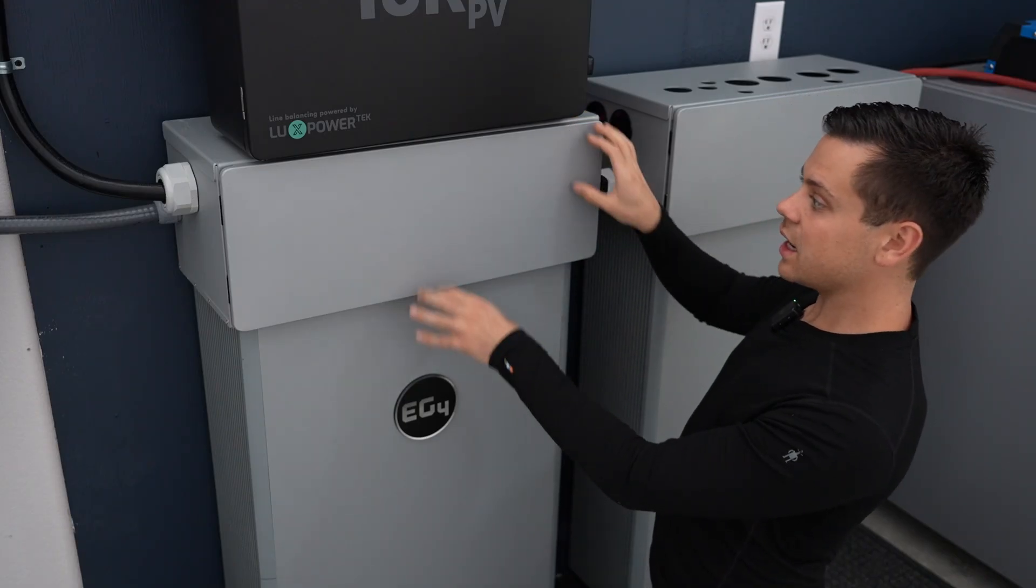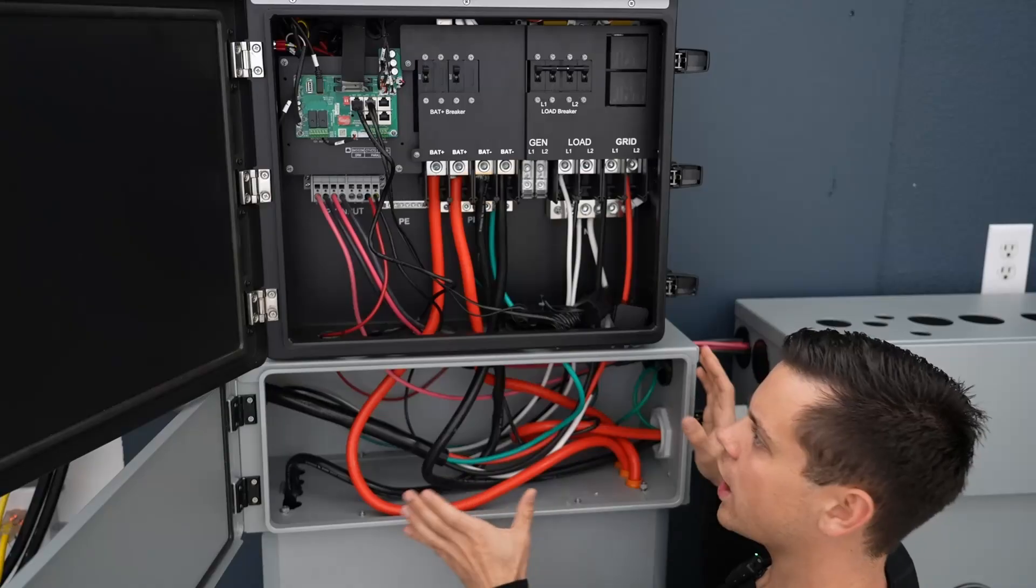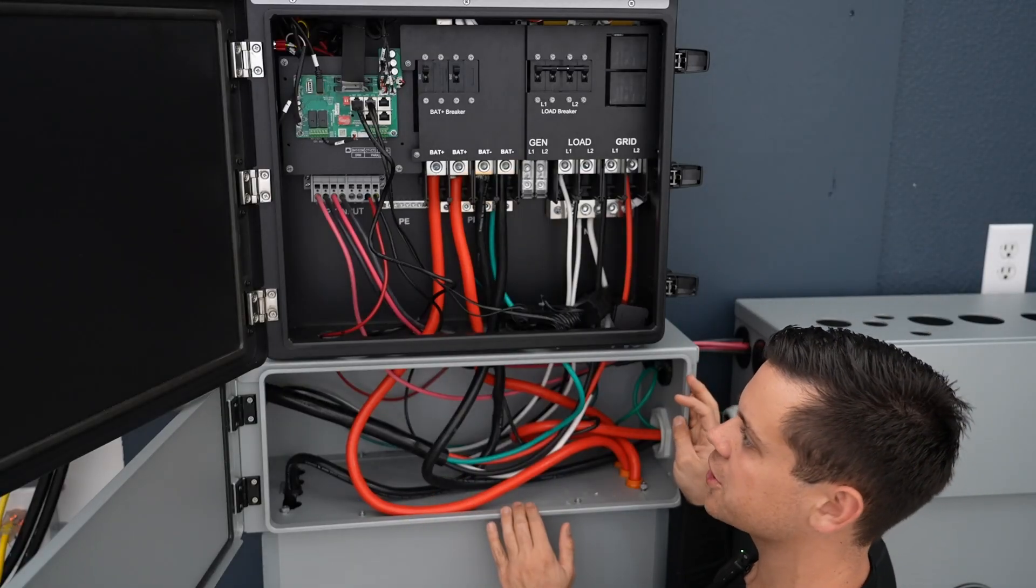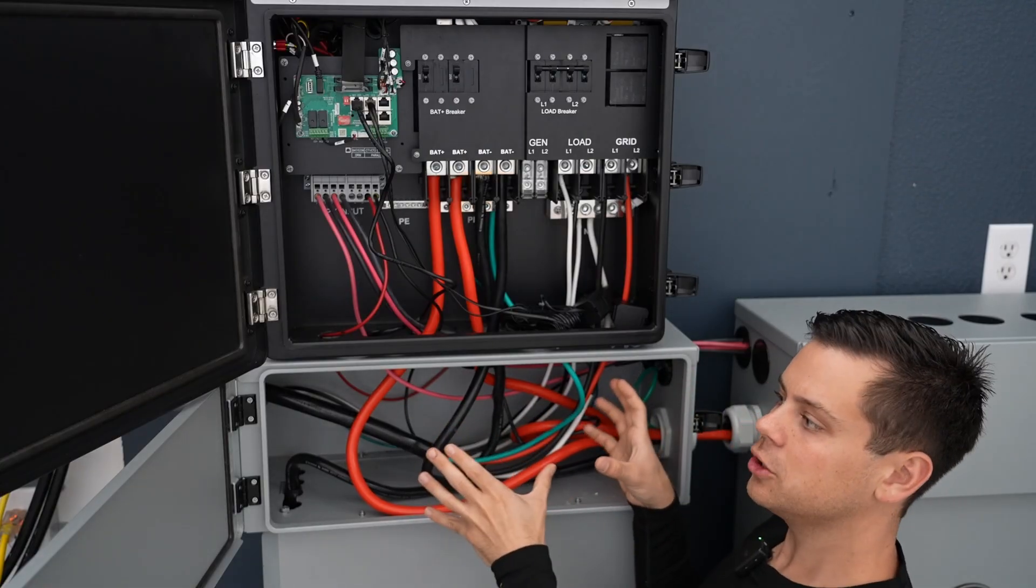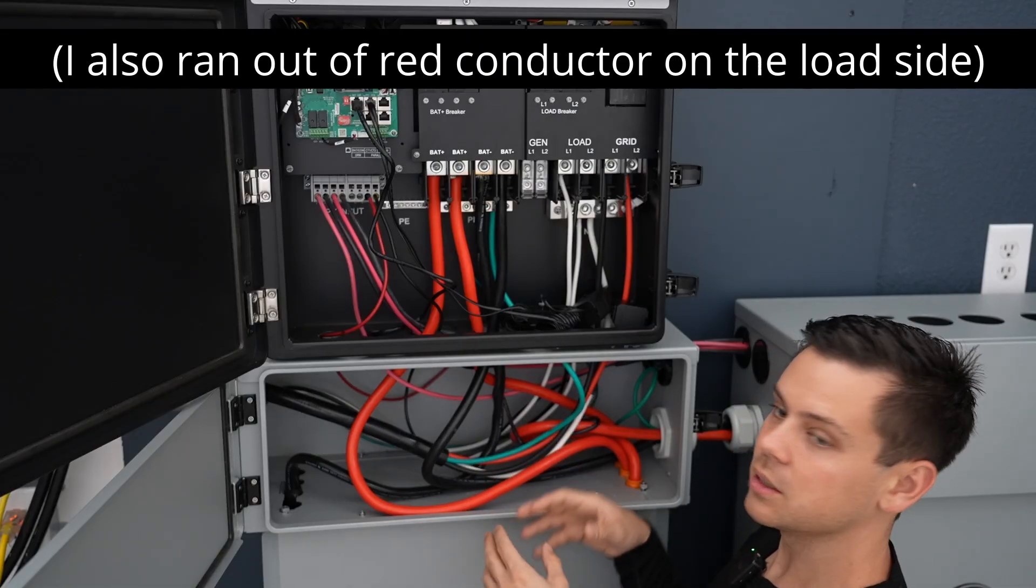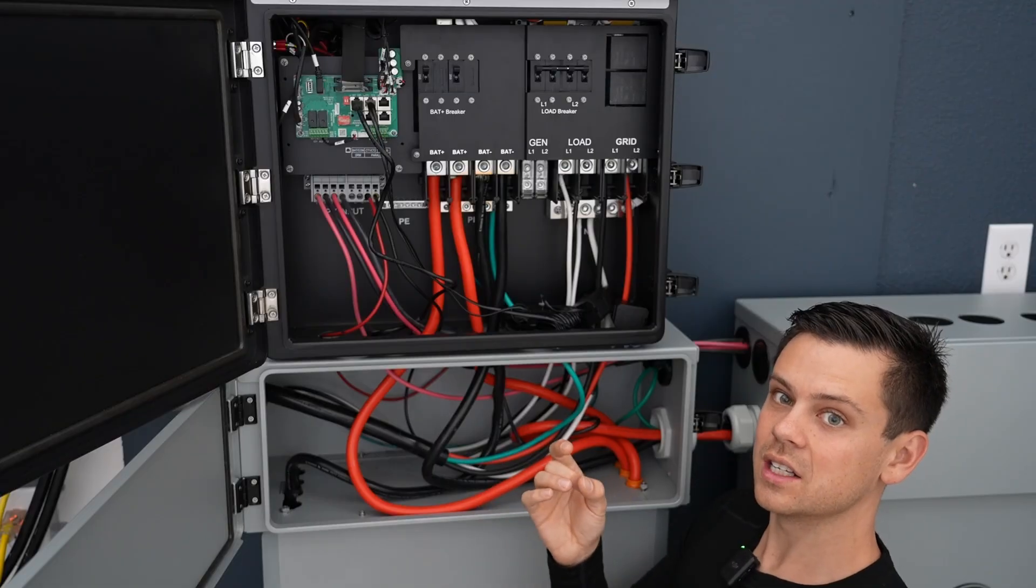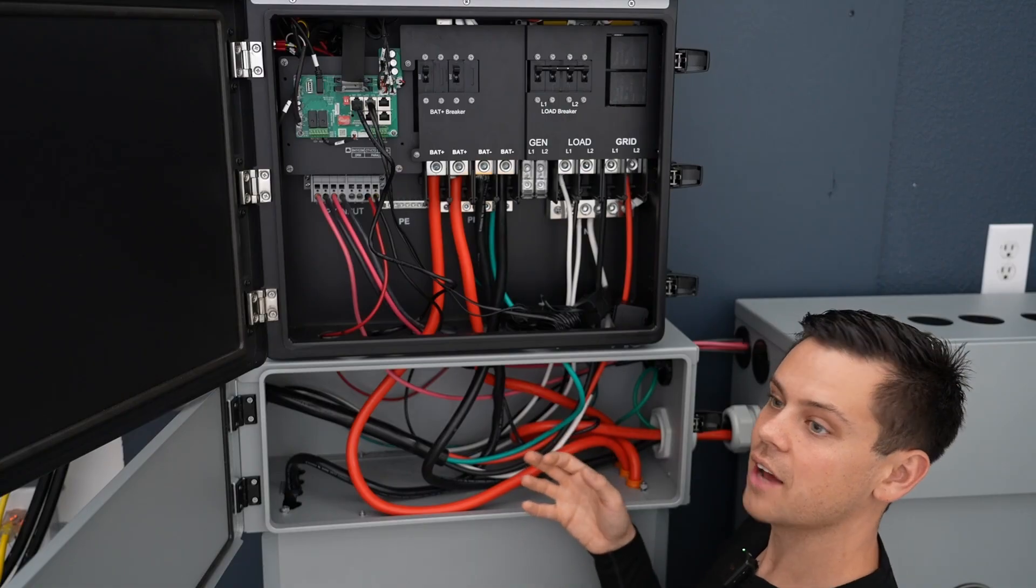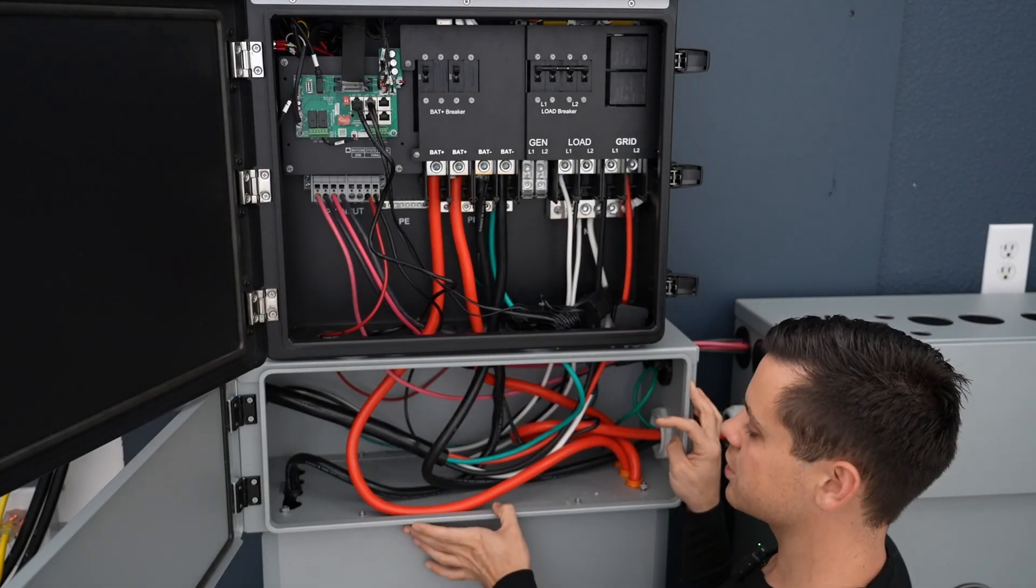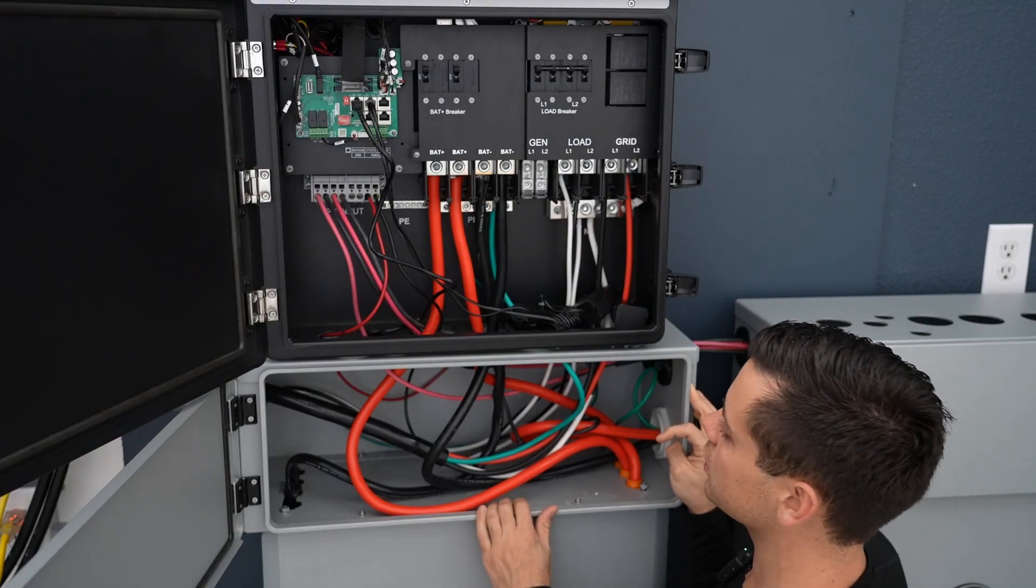So what I did instead is I mounted the combiner box to this board behind it. Now wiring this system was very easy and it didn't take that much time. It looks pretty messy with the PV wires but I don't want anything bundled because I want everything to be able to have its own room and to be able to dissipate heat. When you bundle up large DC conductors close to each other and you're running large loads it's just a bad idea and you're going to have heat spots. So I'm going to hit this with a heat camera, make sure nothing is creating too much heat in one spot and then we'll be good to go.